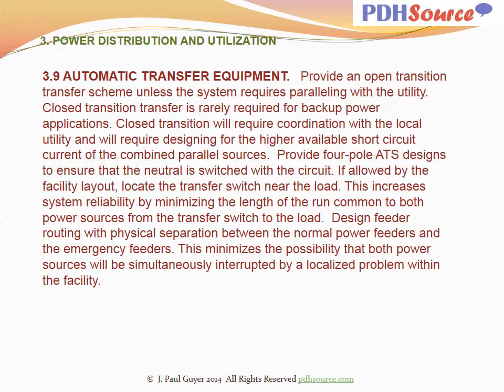Provide four-pole ATS designs to ensure that the neutral is switched with the circuit. If allowed by the facility layout, locate the transfer switch near the load. This increases system reliability by minimizing the length of the run common to both power sources from the transfer switch to the load. Design feeder routing with physical separation between the normal power feeders and the emergency feeders. This minimizes the possibility that both power sources will be simultaneously interrupted by a localized problem within the facility.